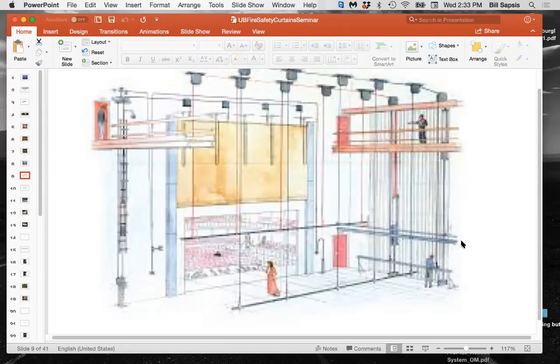Just understand that it's my experience that every time, 100%, every time that smoke doors have been tested, the end result was, once they managed to get them closed again, they never seal properly, and you have water issues coming in.